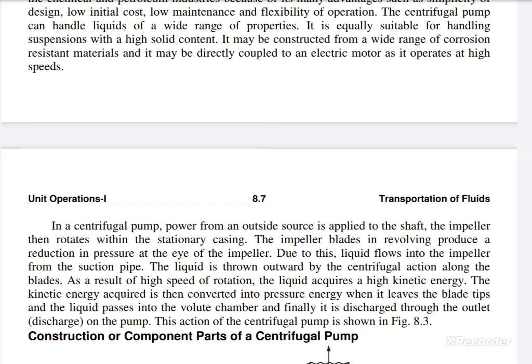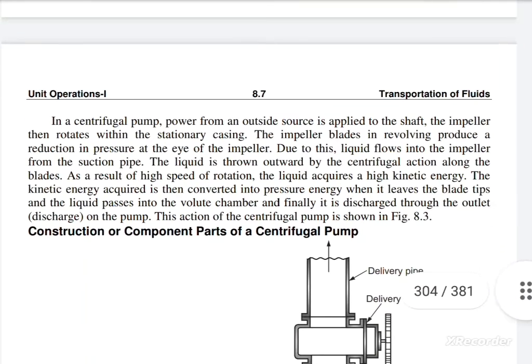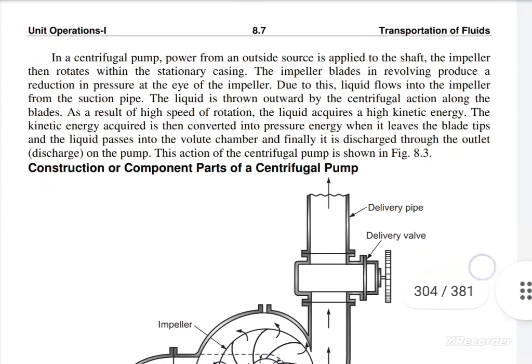As a result of the high speed of rotation, the liquid acquires a high kinetic energy. This kinetic energy is then converted into pressure energy when the liquid leaves the blades, passes into the volute chamber, and is finally discharged through the outlet discharge of the pump. The action of the centrifugal pump is shown in the figure.